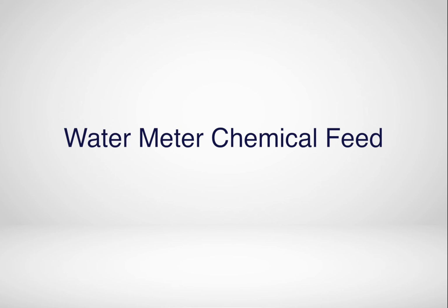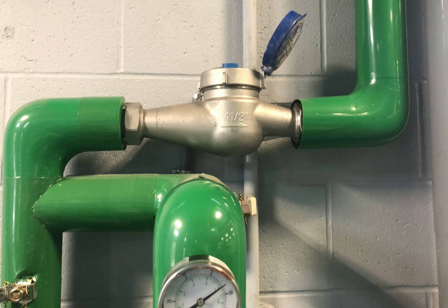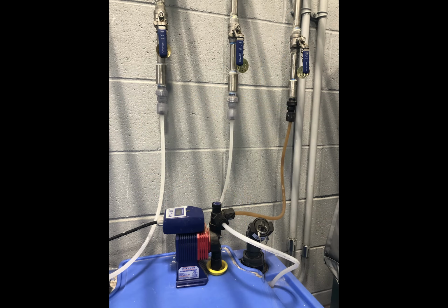Items to check to make sure your chemical feed system is working correctly. Make sure the water meter is registered on the controller by checking the controller menu for gallons of makeup water. And make sure the pumps are coming on with the correct water meter addition and the correct amount of time.